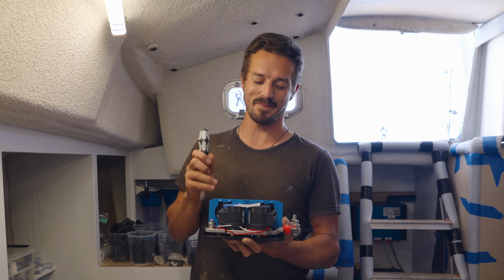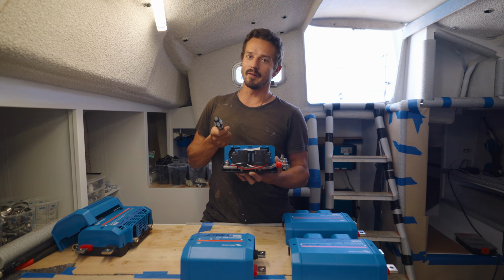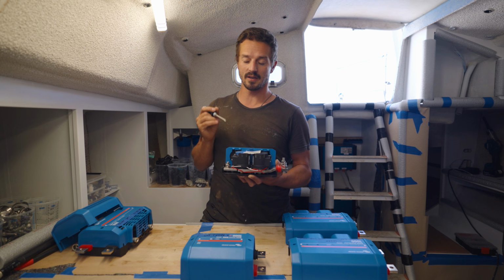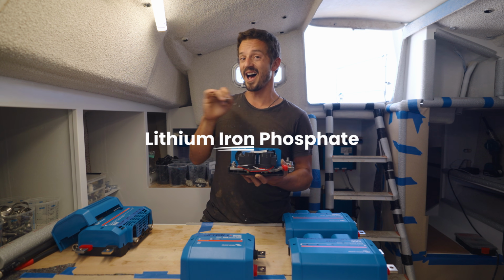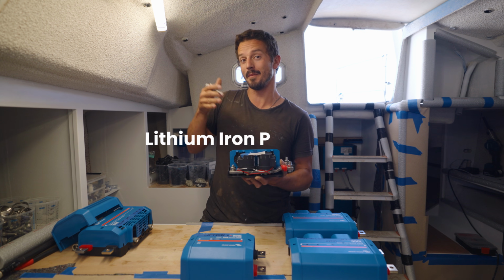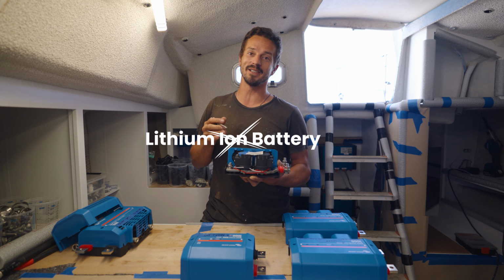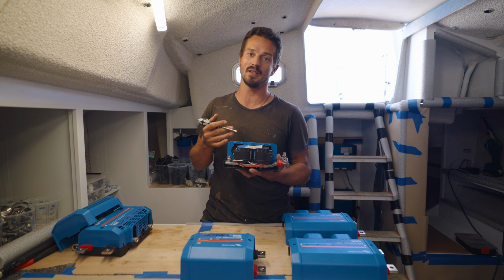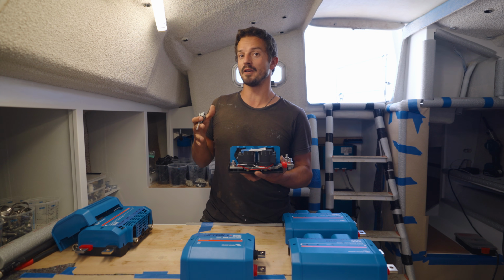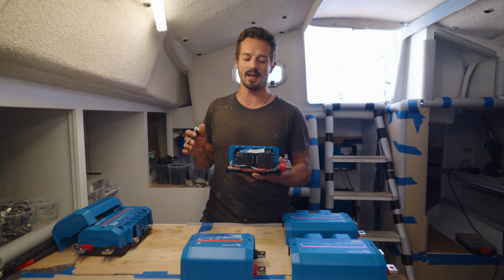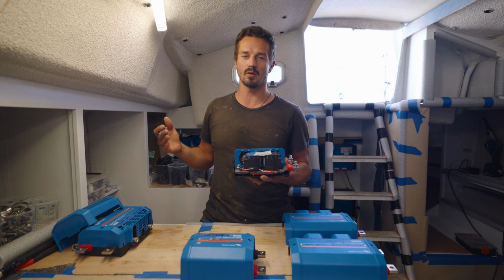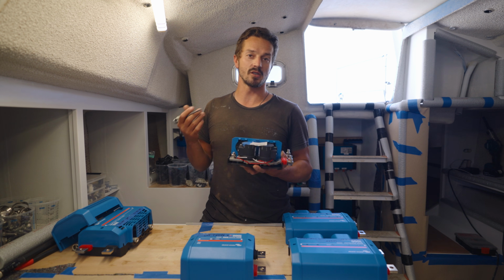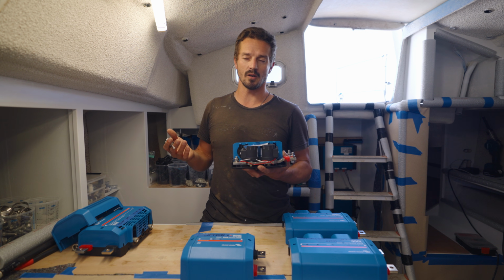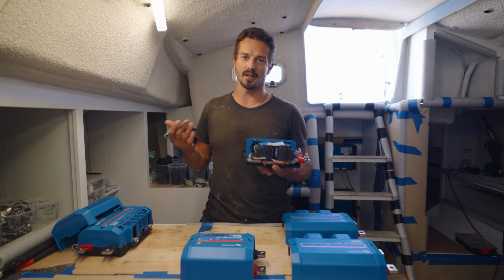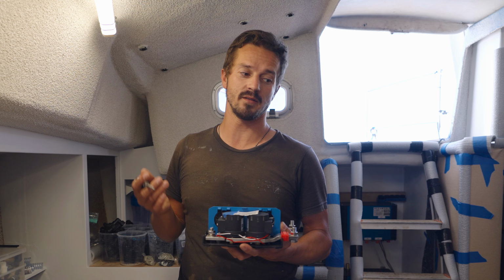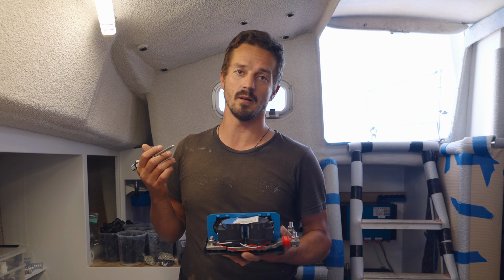I know we joked earlier that the BMS's job is to make sure the boat doesn't catch on fire. That may have been a bit for dramatic effect, because we're using lithium iron phosphate batteries, not lithium ion batteries. There's a big difference in how those chemistries react when they fault. Lithium iron batteries are pretty much the standard in boats these days. When they have some sort of issue or thermal runaway, they just smoke - they don't actually go up in flame. So it's good to vent that smoke overboard, but it's not going to catch the boat on fire. They're incredibly safe compared to the stuff in your phone or in some electric cars.